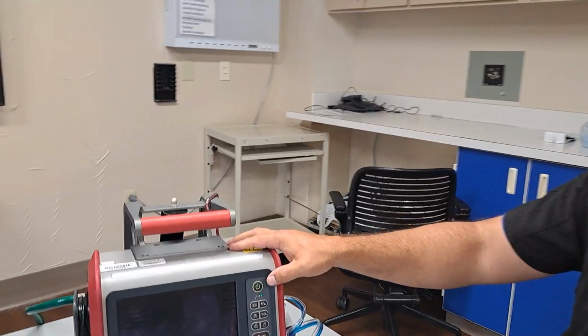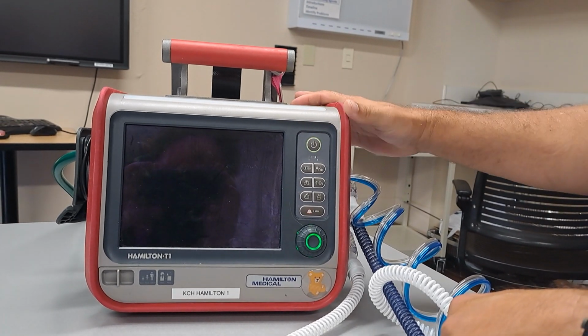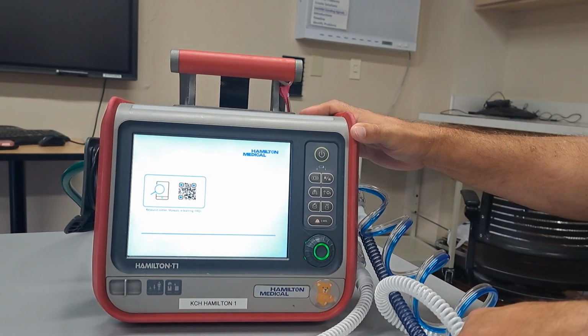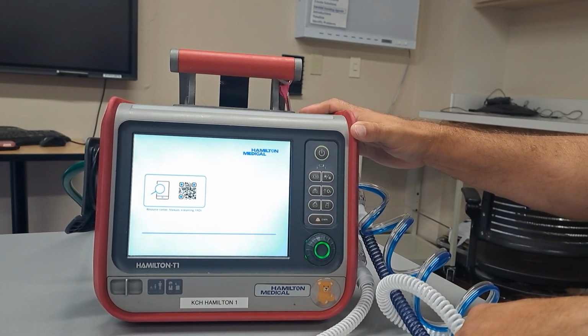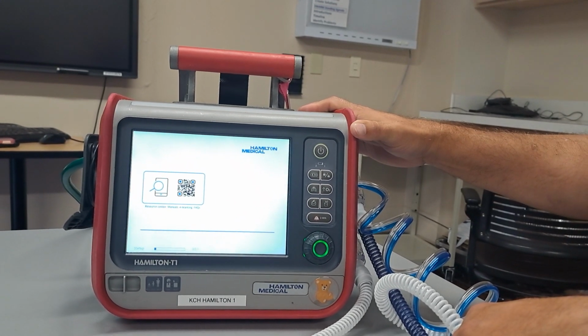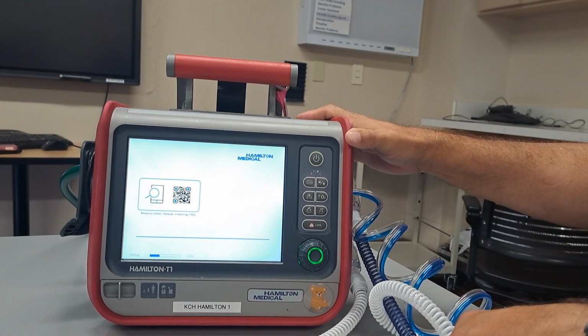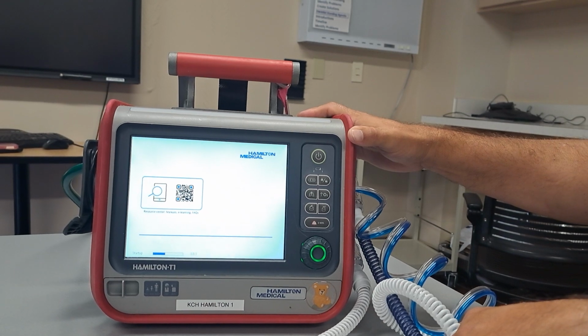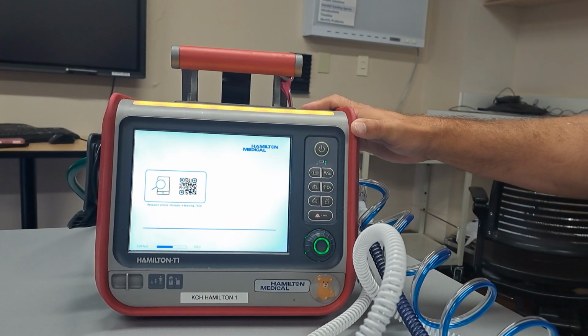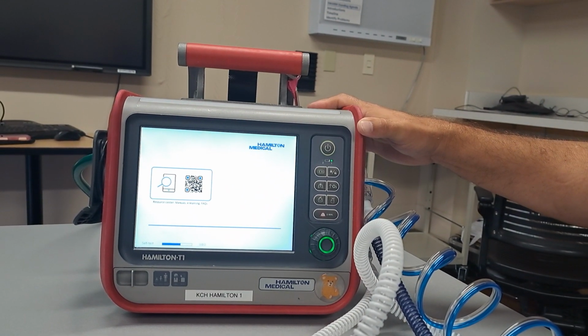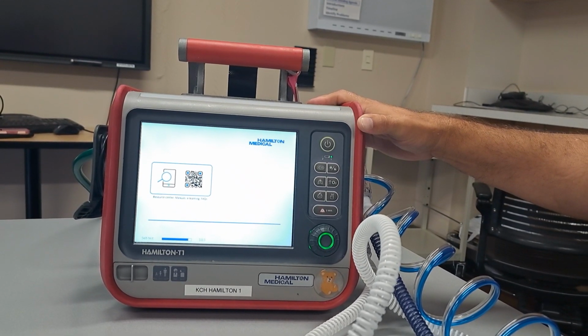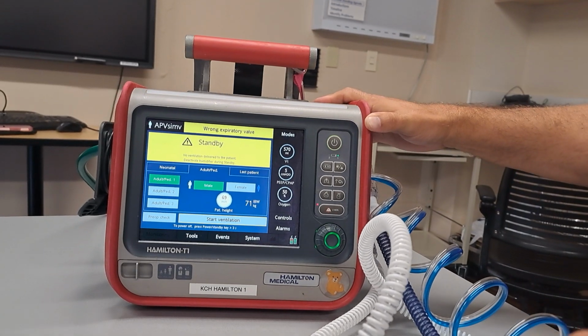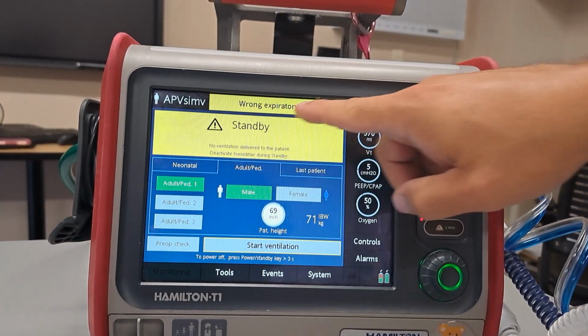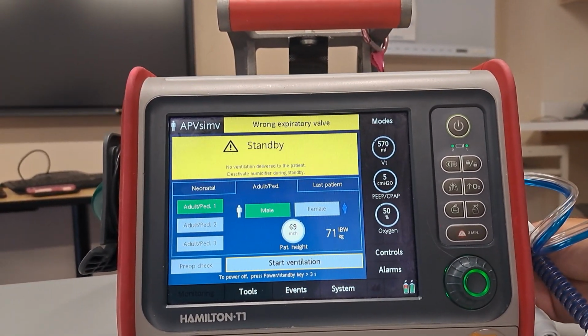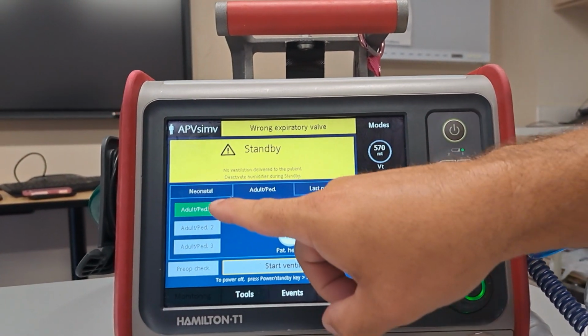So now we will turn the unit on and put it through its pre-use test. So to turn it on, you press the power button. And then it will run a self-test, a pretty quick self-test. Self-test is done. Now, if you notice at the top, it says wrong expiratory valve. Because this is a neonatal circuit with a neonatal valve, we have to be in the neonatal mode.